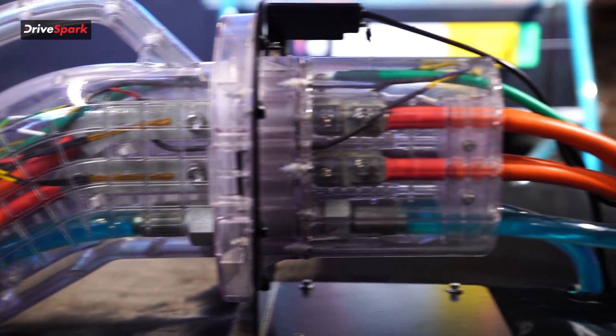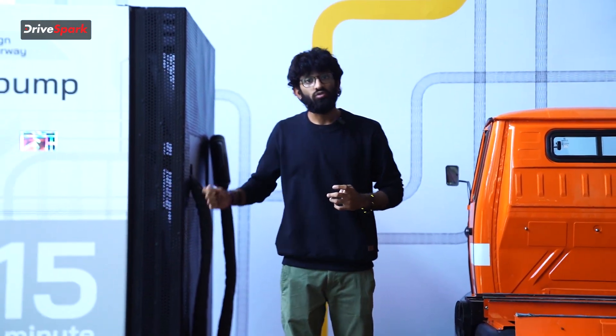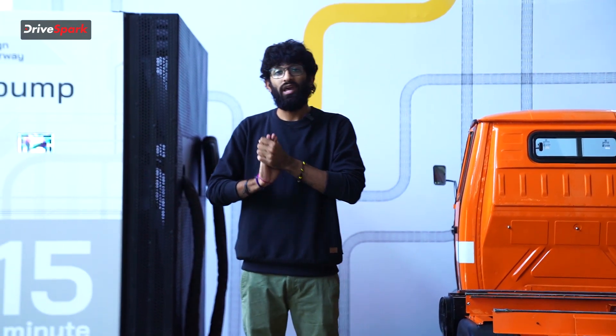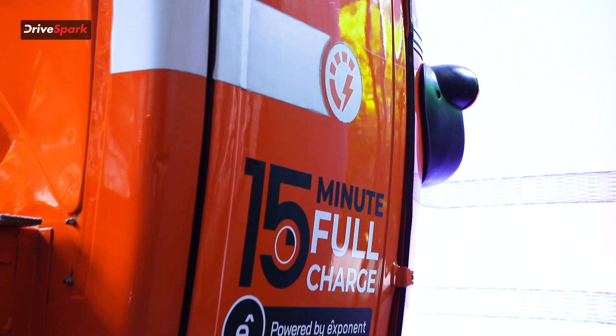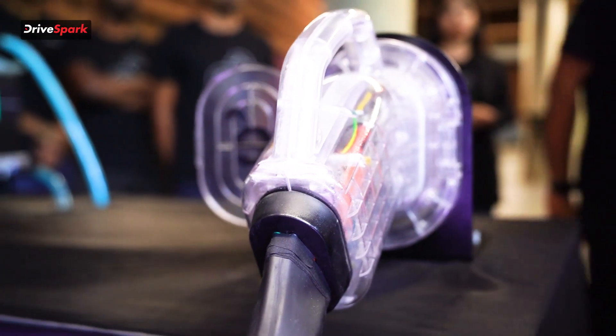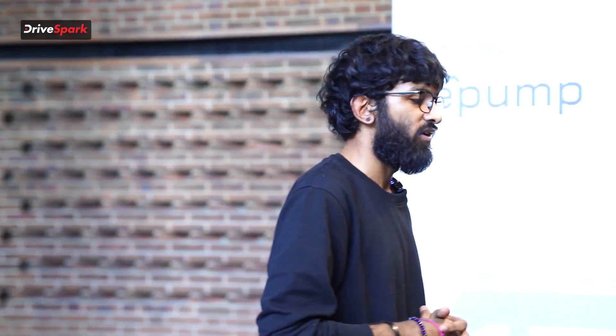How does Exponent Energy keep the batteries at an ideal temperature for so long? They have refrigerated water stored at 10 degrees Celsius in that pump, which when you charge also shoots the water into the battery — kept in a safe place to avoid any problems inside the battery. To take a closer look at this whole procedure, Exponent has set up a makeshift visible demo rig that we can see over here.